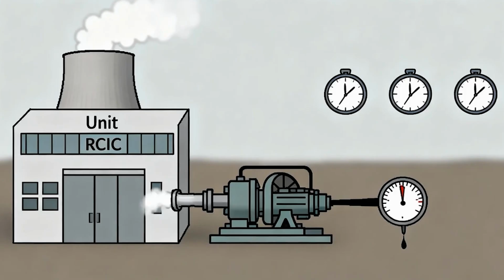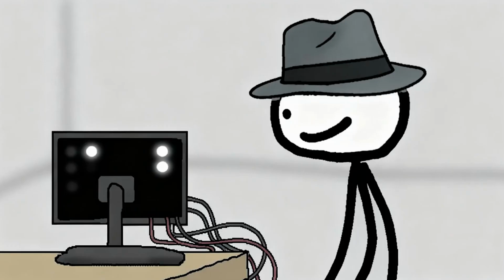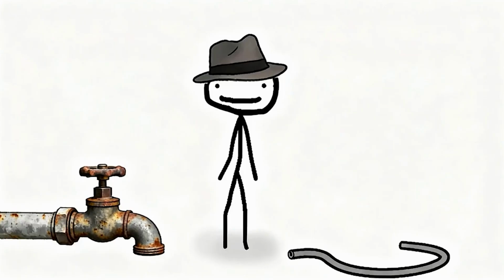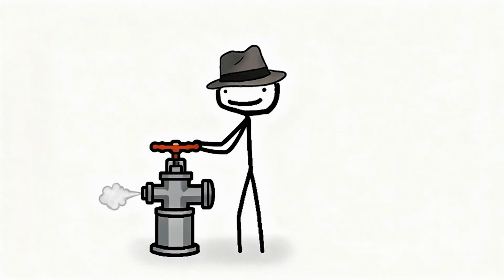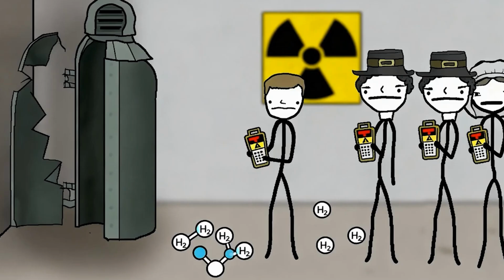Unit 2's RCIC kept running for more than 3 days before steam pressure dropped too low. Unit 3's systems failed within 20 to 68 hours. Without AC power to recharge batteries or run pumps, operators had no way to inject fresh water once those steam-driven backups quit. Safety relief valves were used to vent pressure and try alternative injection methods, but delays in venting, caused by radiation levels and equipment failures, led to more hydrogen buildup.